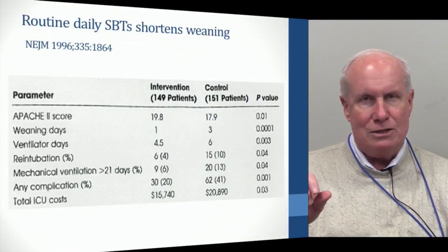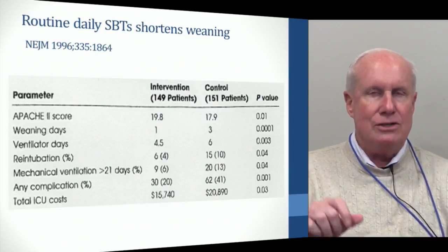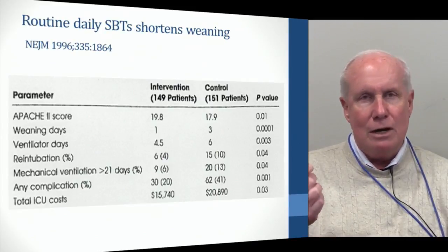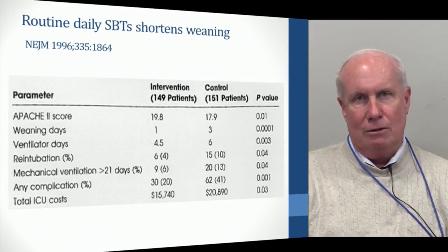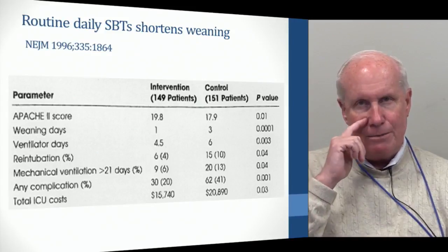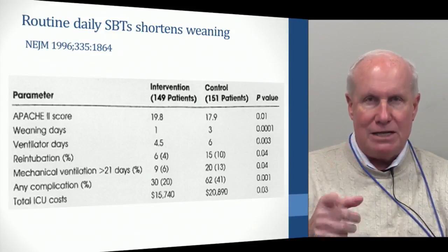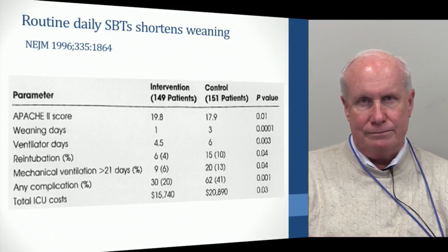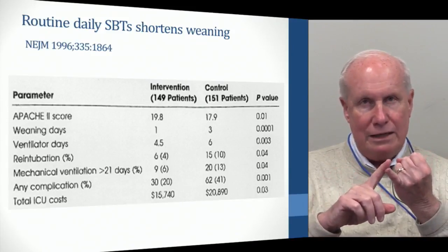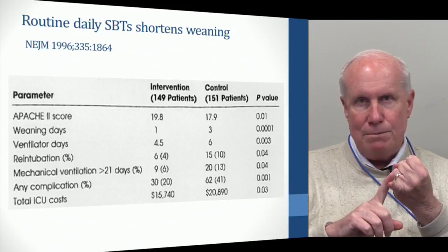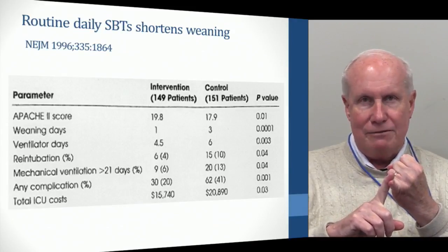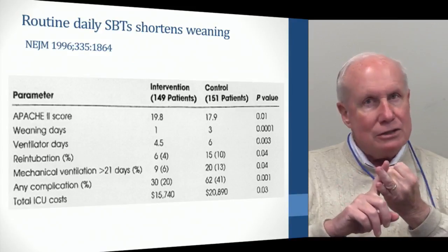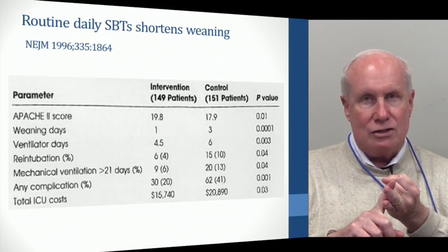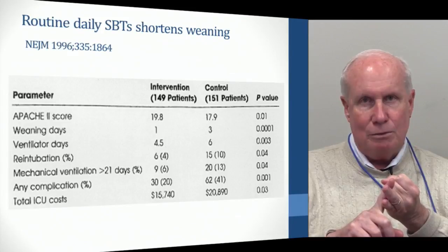There's no adjustments of inspiratory pressure. There are no adjustments in respiratory rate. There is no technical weaning going on here. The only thing that's happening here is a daily spontaneous breathing trial. So our rule around here is if the FiO2 and the PEEP are in a safe range, less than 40%, PEEP of less than 5 to 8, and the patient can trigger the ventilator, it's time to do a spontaneous breathing trial.